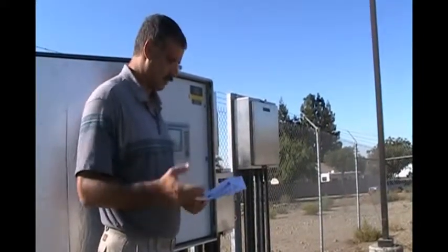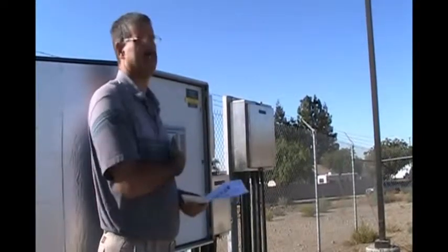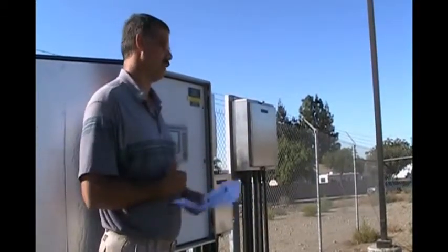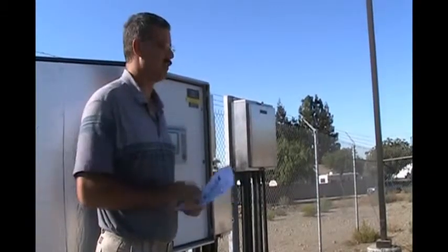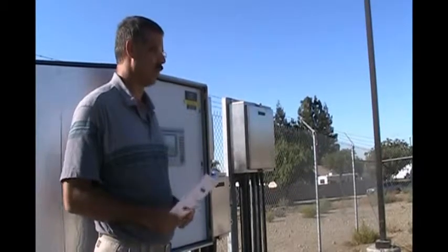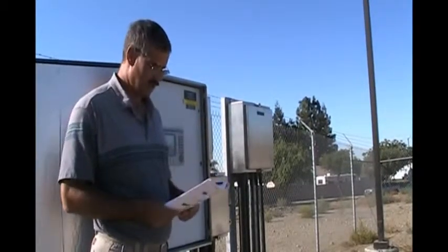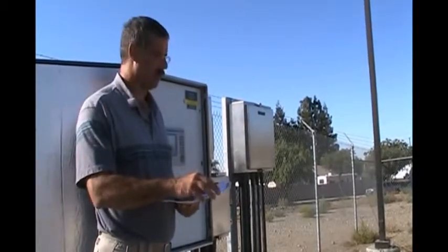Common alarms are going to be too high on our pressure, too low on our pressure, too much flow, too little flow, or failure with some of our equipment. We do have our bad signals, which is our open circuit for all our analogs, and we have a few things for power monitoring, such as AC and DC power monitoring.